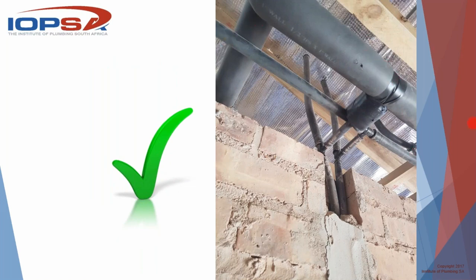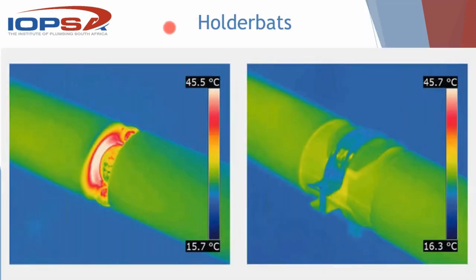So it's all doable. And just for show and tell, this is a FLIR image of a bracket or a holder bat, one over the lagging, one not over the lagging. You can see immediately the heat loss that occurs around the bracket when you've stopped the lagging short and then started again after the bracket. That little band of heat loss is present if you're looking at it from the other side as well. So there are a lot of little areas in each bracket where you'll lose a lot of heat.